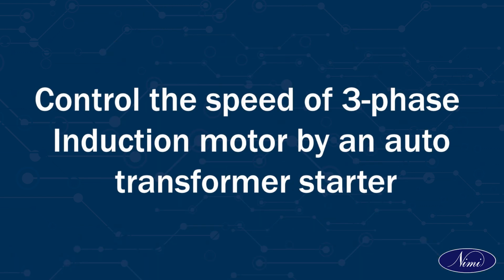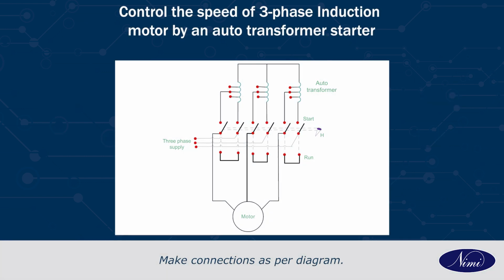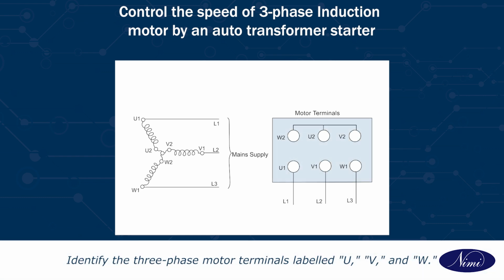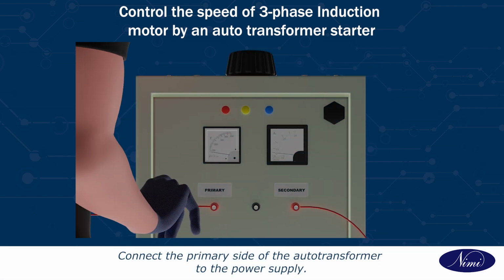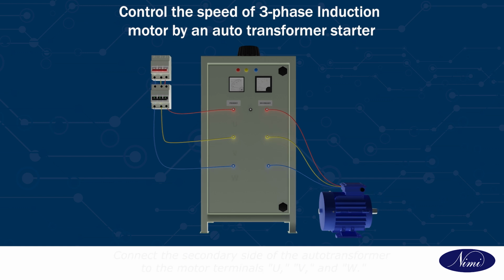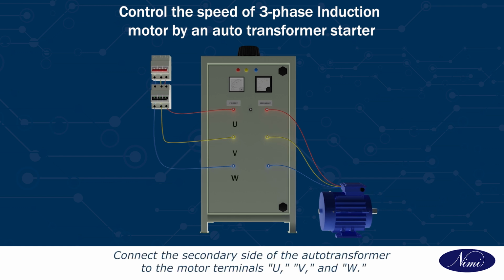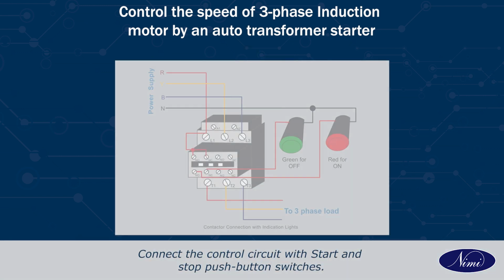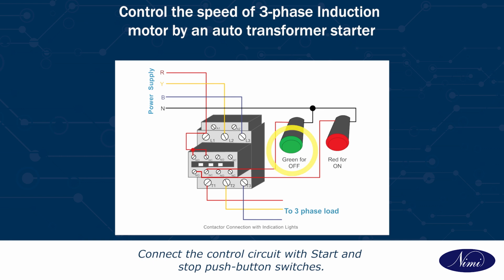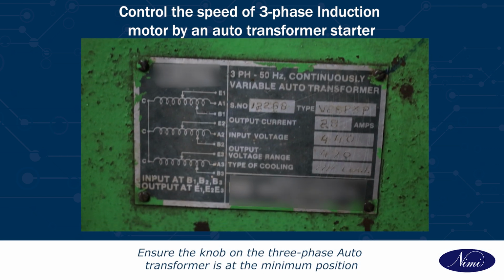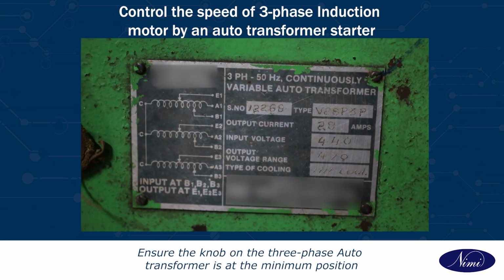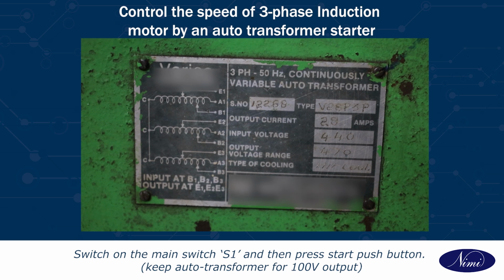Control the speed of three-phase induction motor by an auto transformer starter. Make connections as per diagram. Identify the three-phase motor terminals labeled U, V and W. Connect the primary side of the auto transformer to the power supply. Connect the secondary side of the auto transformer to the motor terminals U, V and W. Connect the control circuit with start and stop push button switches. Ensure the knob of the three-phase auto transformer is at the minimum position. Switch on the main switch S1 and then press start push button.